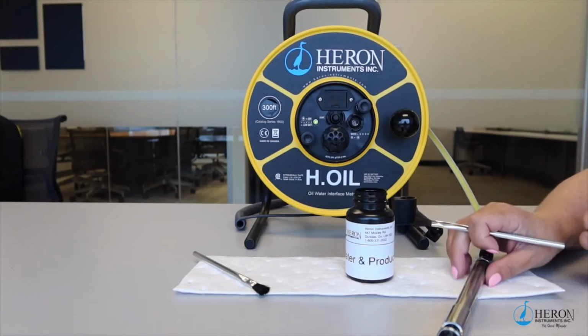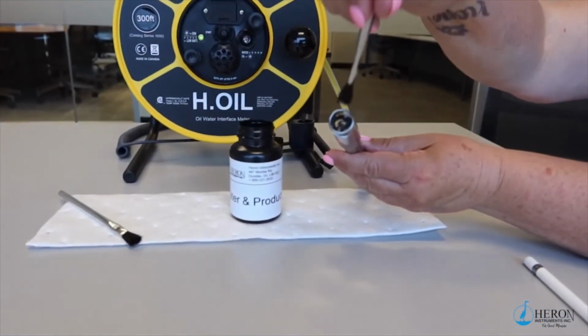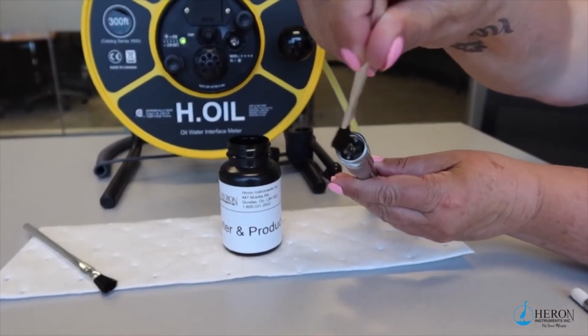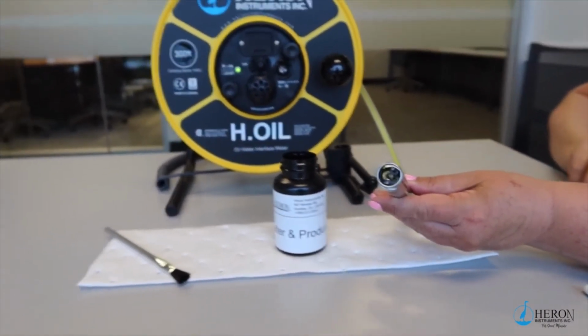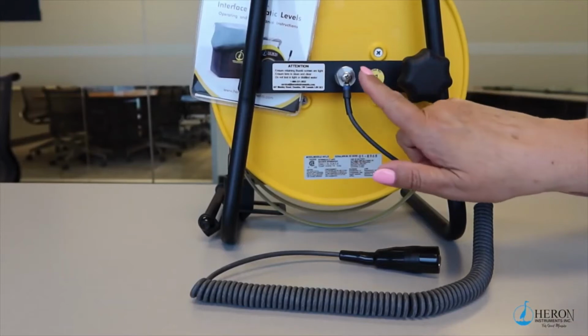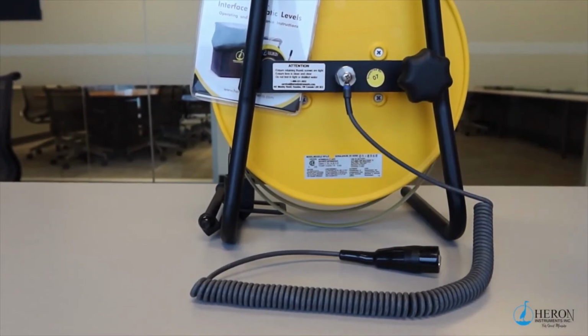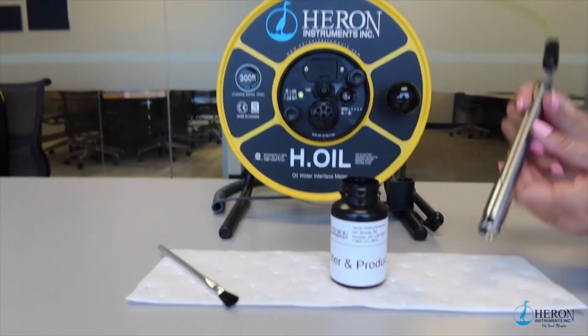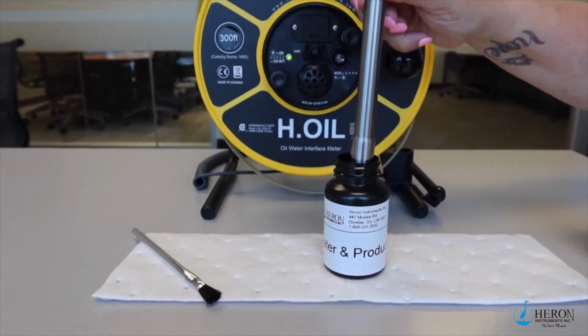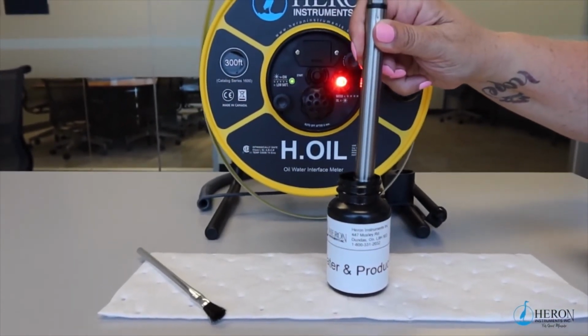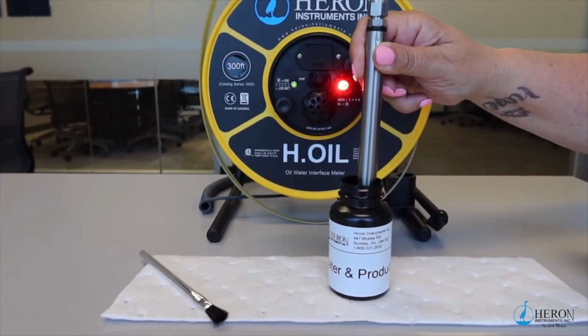Make sure the lens is clean and clear before use. To maintain intrinsic safety, ensure the ground lead is securely fastened to the back of the frame and in good condition. Test the probe in the provided test bottle. Note, the probe will not work in ambient light conditions. The probe needs to be shielded from light.